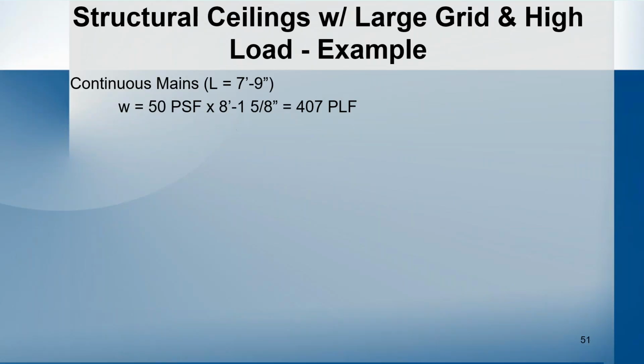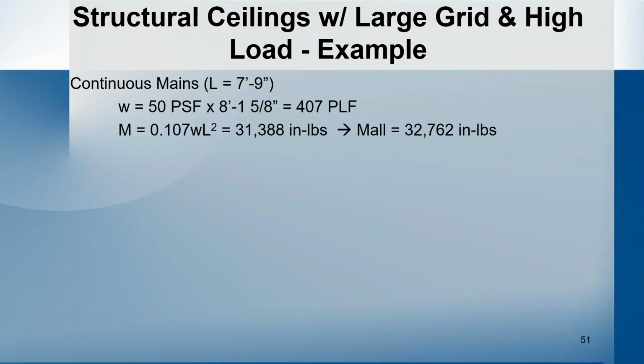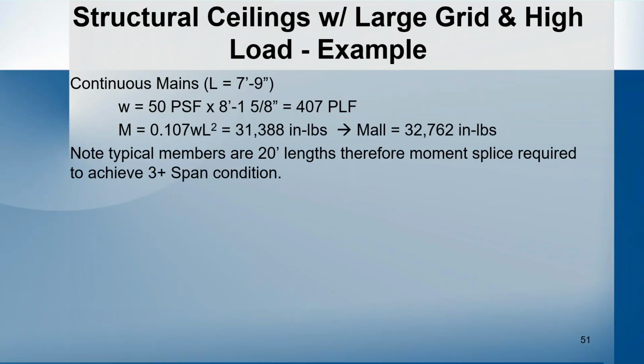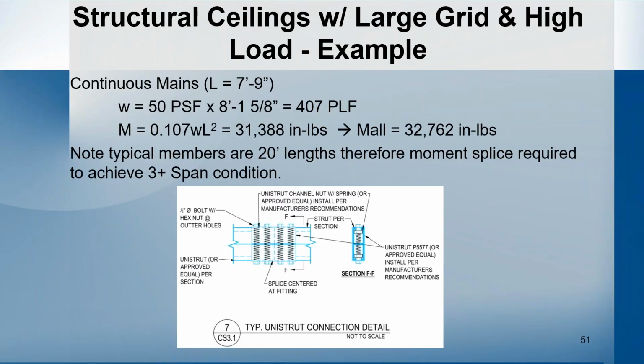So then for your continuous member, these ones typically will be 20-foot long sticks of strut. That's what they typically sell in. So we have the same 407 PLF. This one's running continuous between the members, so at every single steel beam, you're dropping directly from the steel beam. In this case, we have a little bit of relief on our design. So we're able to get, it works at the 8 foot bracing. However, we do need to make sure that we are splicing it with a moment splice.